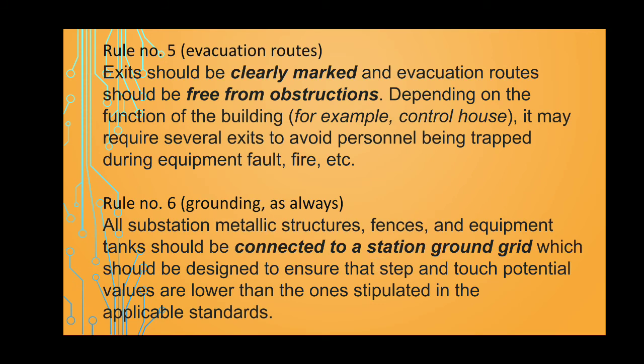Next, rule number 5 is evacuation routes. Exits should be clearly marked and the evacuation route should be free from obstruction. These all depend on the function of the buildings. For example, in a control house, several exits may be required to avoid personnel being trapped during equipment faults, such as a fire developing in the electrical substation. So these are also essential things: free from obstruction and clearly marked and indicated.